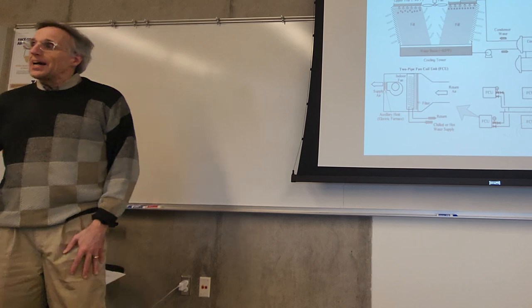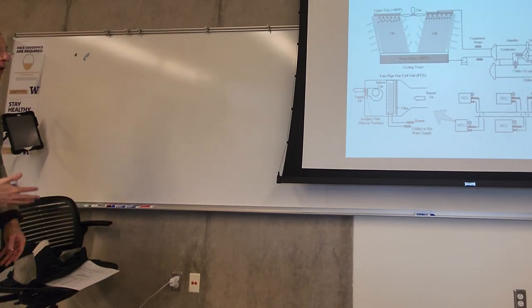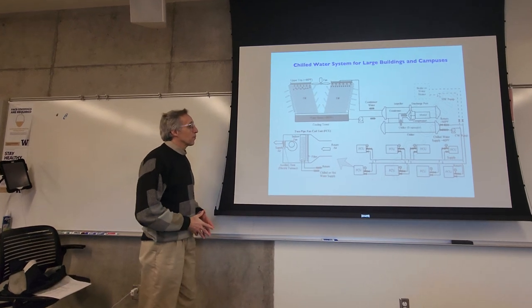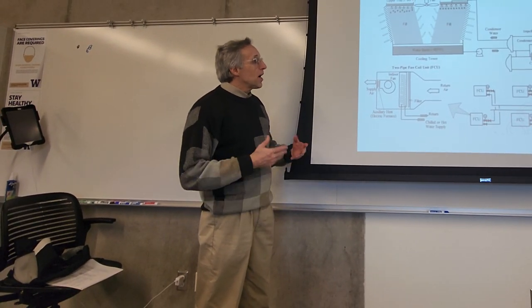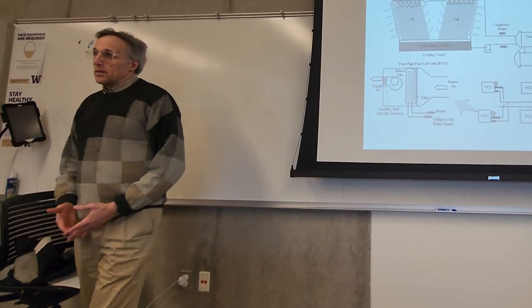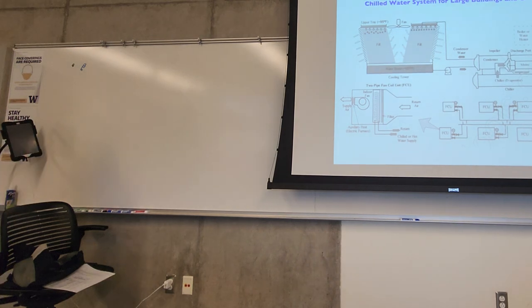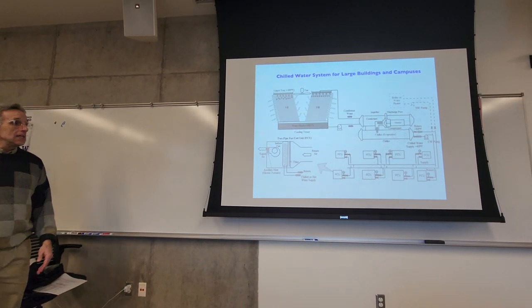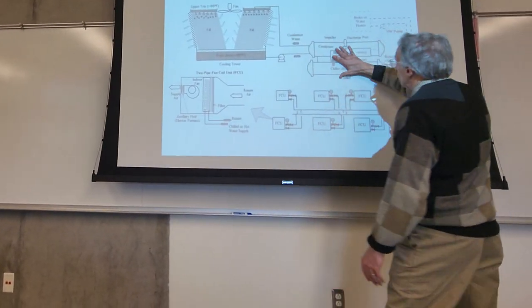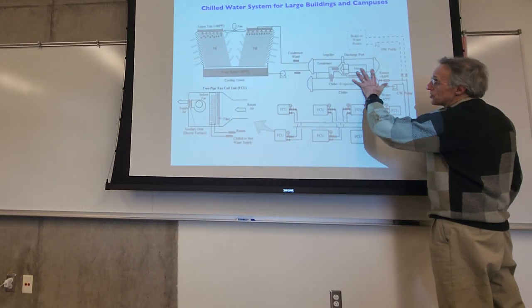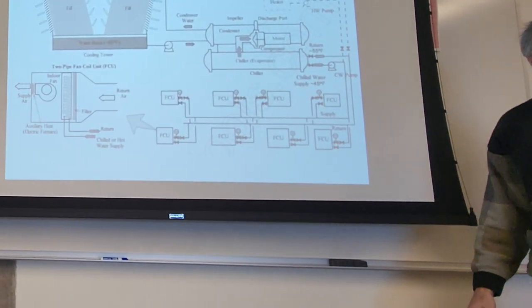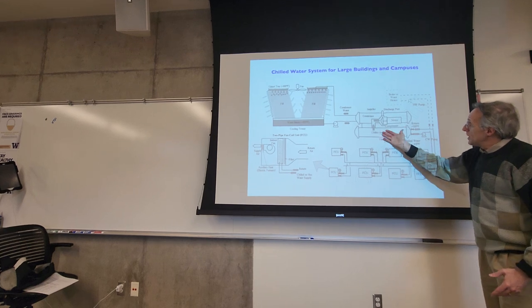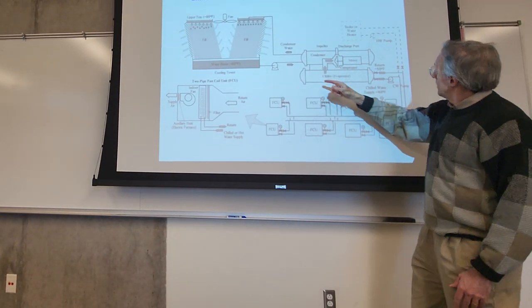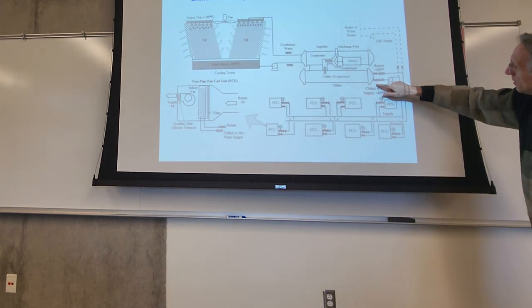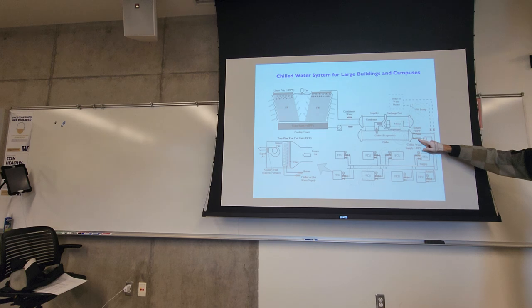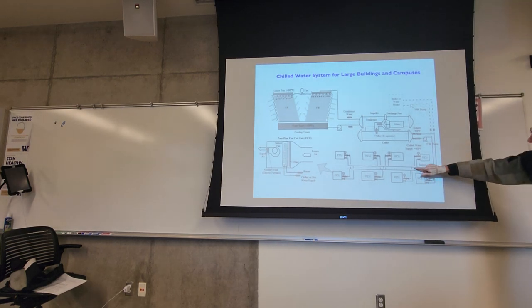And then moving to the most sophisticated level of cooling, when you've got a big building like this where we are here, is a chilled water system. And now you're not refrigerating the air directly, but you're using cold water as an intermediary, or hot water if you're heating. So now the refrigeration unit is big enough that it's just a separate piece of hardware that sits in a mechanical building somewhere, or in the basement of the building maybe, and it makes cold water, generally about 40 to 45 degrees, and then that goes out to all the places where you want to use it.